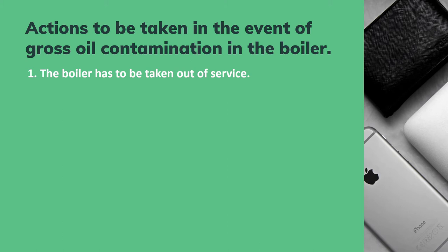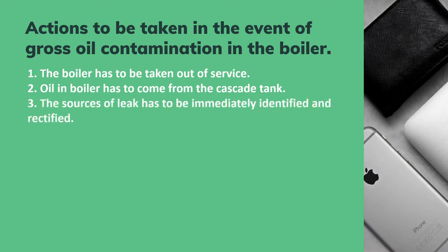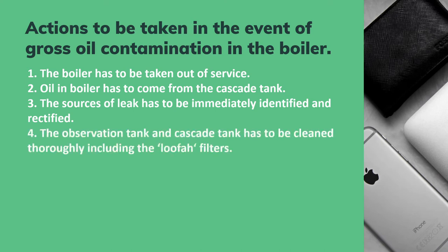Number one: the boiler has to be taken out of service. If there is gross oil contamination, we must stop the boiler and take it out of service. The oil in the boiler must have come from the cascade tank. The source of the leak has to be immediately identified and rectified. The observation tank and cascade tank have to be cleaned thoroughly, including the loofah filters.